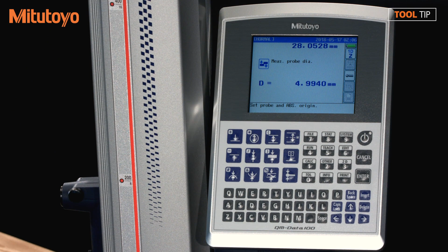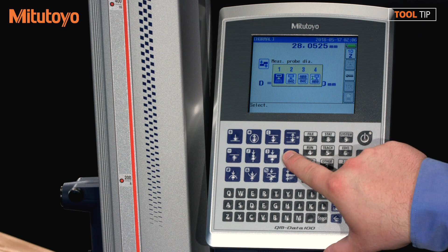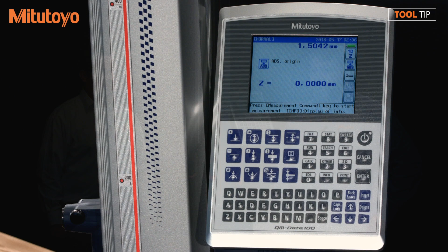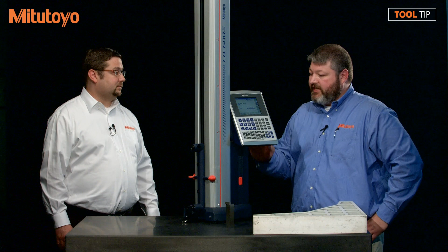So now, Drew, the last thing we have to do is set the absolute origin. To do that, I'm going to hit the datum button, and I'm going to select the first option to just measure down. Now the probe's made contact with the granite, and you can see back on the display that the granite now measures 0. Well, that's pretty easy to get up and going, and it didn't take very much time at all. No, it's actually very easy to get going. It's quick. The gauge is now ready to use.